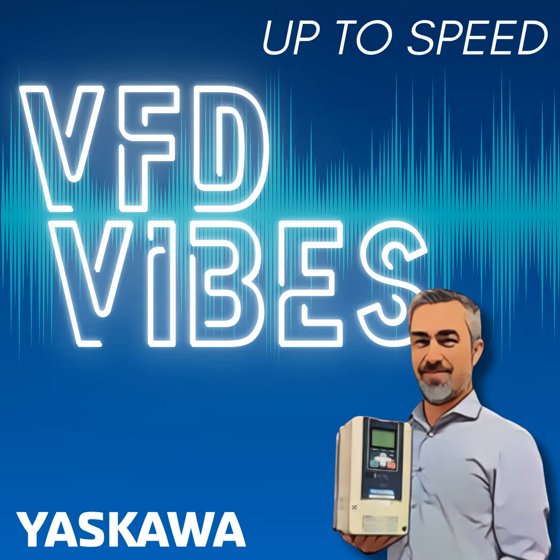Think of your VFD as part of a larger ecosystem: motor, cabling, load, and environment. Each of those elements can either boost your efficiency or quietly drain it away if overlooked. A properly installed VFD can last for decades, especially with Yaskawa's quality. But a poorly installed one can fail long before its time. So let's start with installation.